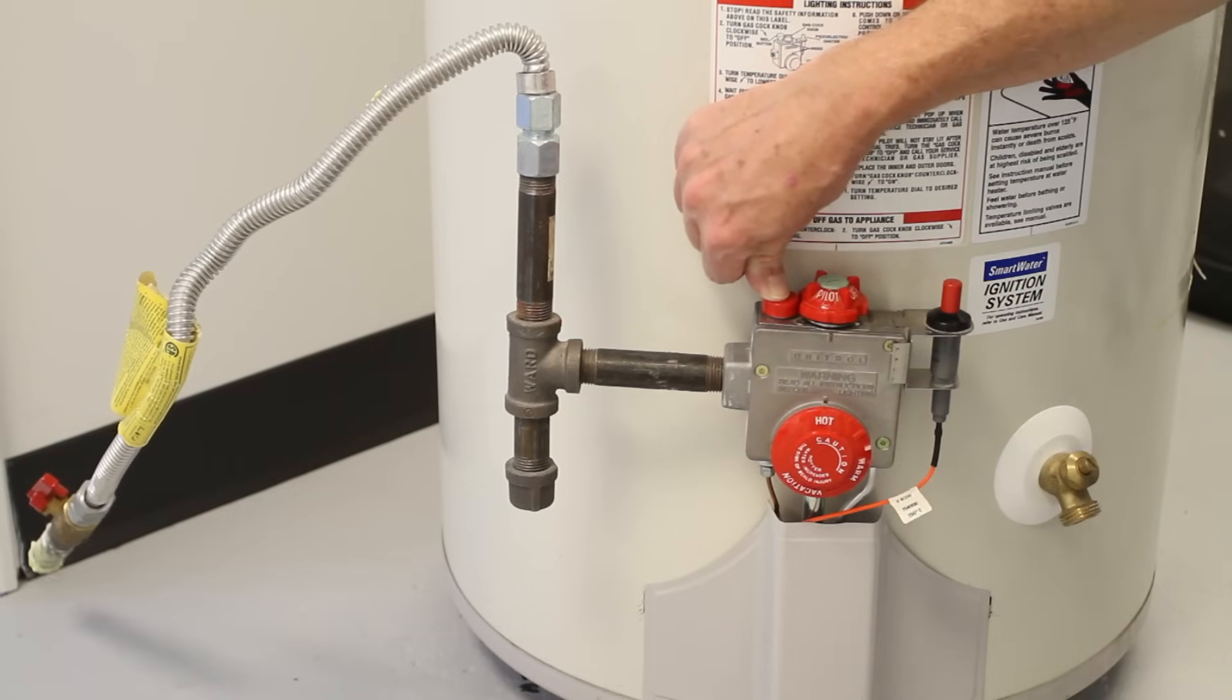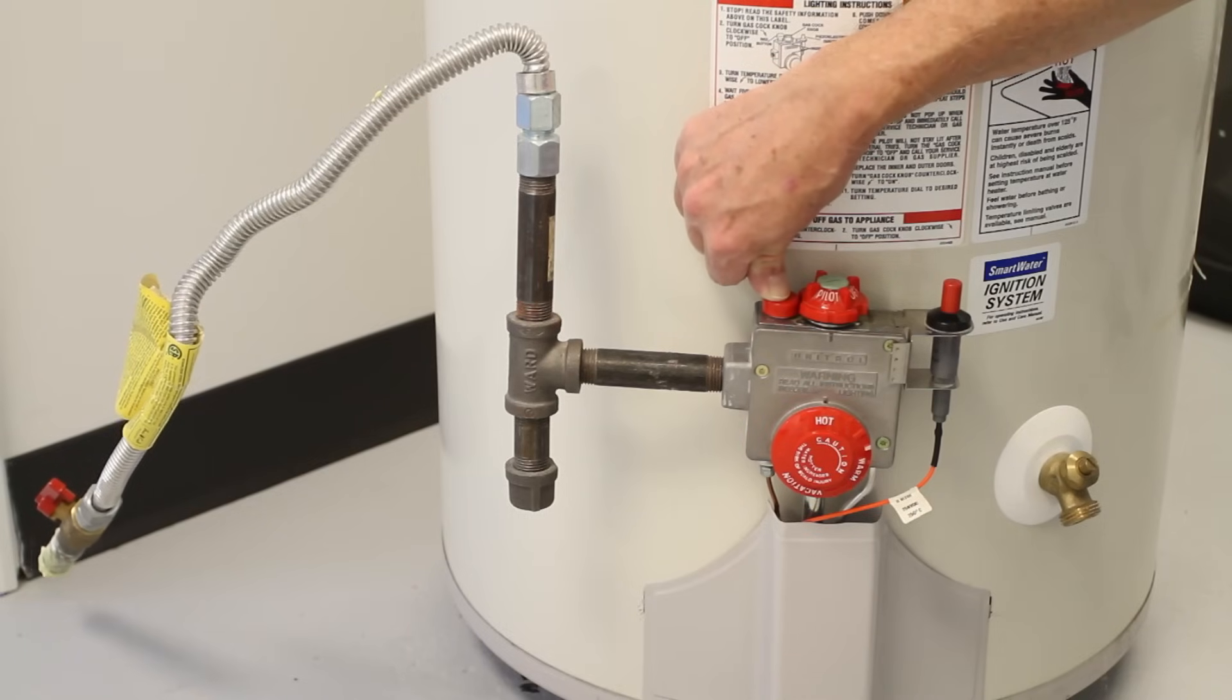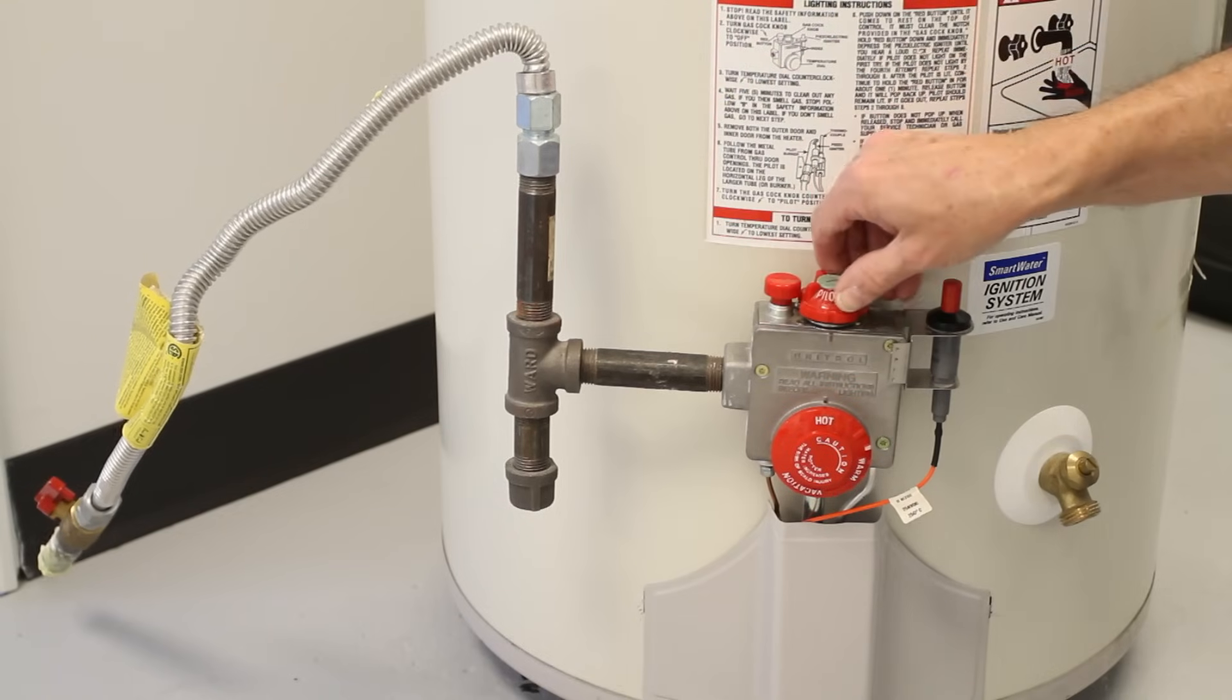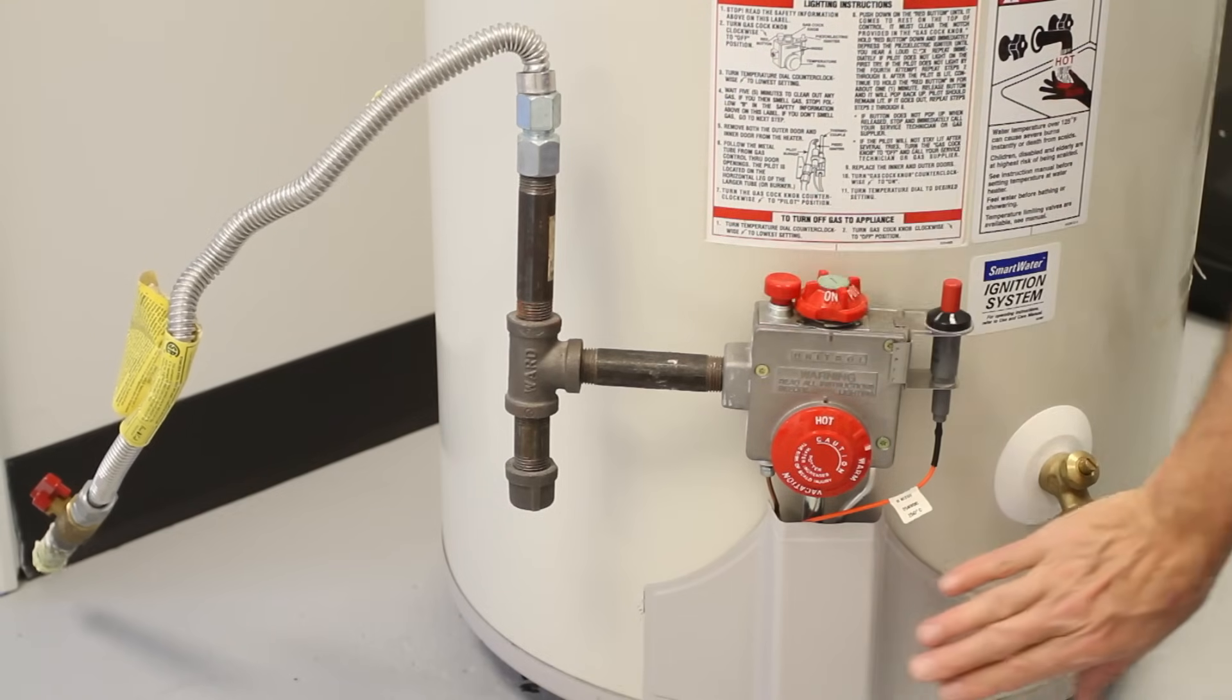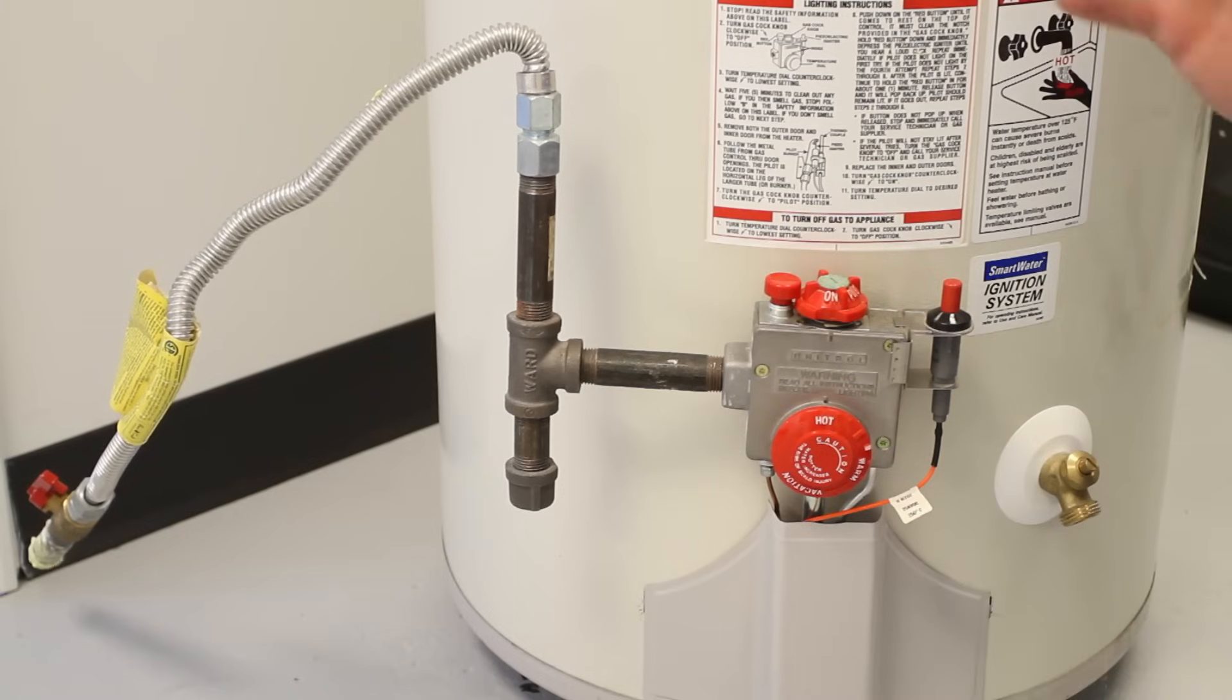And then here's the most important part. You continue to hold that button down for about 60 seconds. When you've done it long enough, let this go, turn this to on, and you should hear the burner come on. And that's when the water will start to heat.